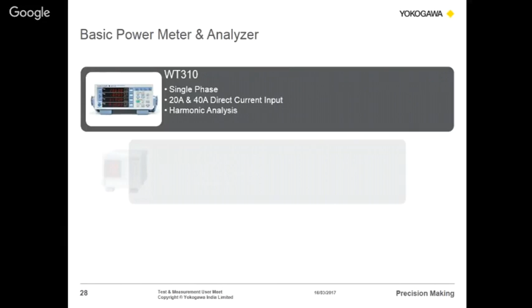Or if you want to measure more than 40 amps, you can connect through a sensor, CT or Hall effect sensors. You can connect it to the equipment and measure up to kiloamps, and harmonics up to 50th order. You have the WT330 3-phase power meter, 20 amps direct, and as per the probe or CT selection, you can go to the higher side, with harmonic analysis up to 50th order.